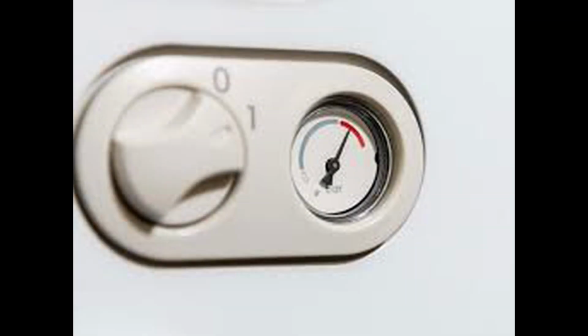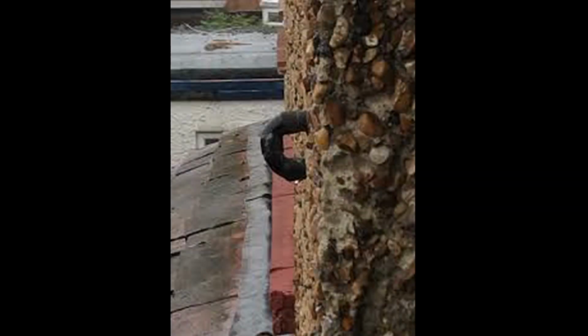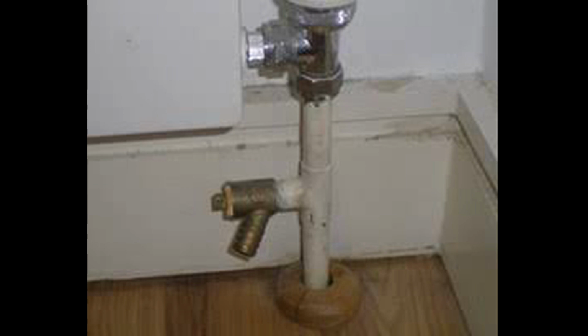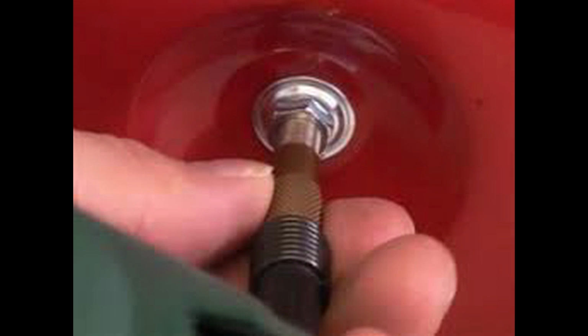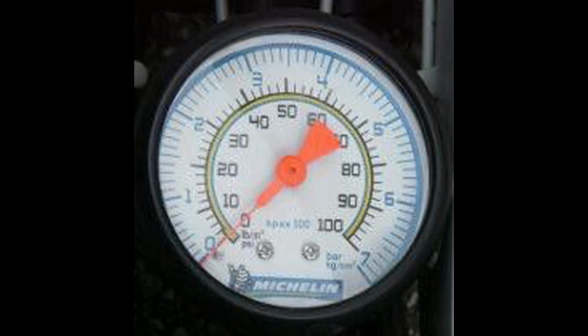Another common problem is the pressure keeps rising above 3 bar and then leaks out of the safety pipe terminated outside. To cure this problem, you should open a drain-off valve on a radiator or even open the bleed valve. Once the pressure has dropped, undo the cap on the Schrader valve on top of the expansion vessel. Attach a foot pump to this valve and pump the gauge to approximately 1 bar. Leave and monitor for 5 minutes. If the gauge on your foot pump drops, then repeat the above process. Once the pressure is stable at 1 bar, remove the foot pump and replace the Schrader valve cap.